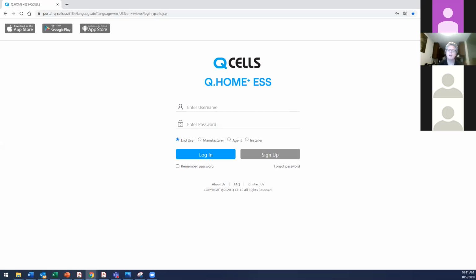Another question: can it work in off-grid mode, like for a cabin with no grid at all? As long as your battery is connected, there's a special operation mode we call black start. In black start mode, you don't need the grid to turn on the system. We can work in grid-tied mode, in off-grid mode, and also in a purely off-grid mode where there's no grid at all. In that special black start mode, we can turn on the battery to support your system and it can just keep working. As long as there's PV, you can also charge the battery. So even without grid, we have this control in the system to turn it on as long as the battery is connected. Yes, we can support that kind of situation too.